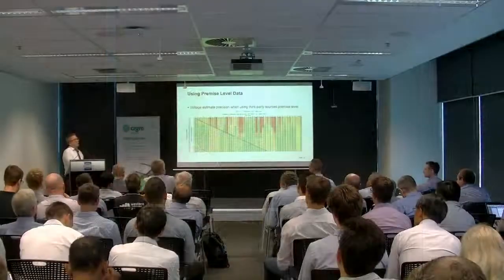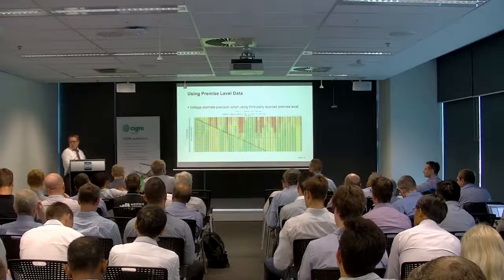That's a similar pattern we saw at the MV level when working with Energix, where the load points measured are the distribution transformers. There too, at about 20% the voltage profile settles, and at about 30-40% the flows towards the infeed start settling. So these tests have been quite informative and relevant, because you really don't need to measure everything. The measurement locations were effectively selected randomly, since we had to ask customers to consent, and not everybody did. So it's a robust process that can ingest that, we can quantify the uncertainty in it, and you don't really need 100% coverage.